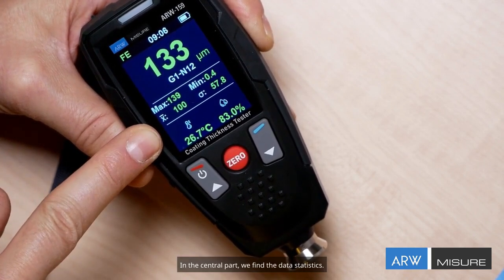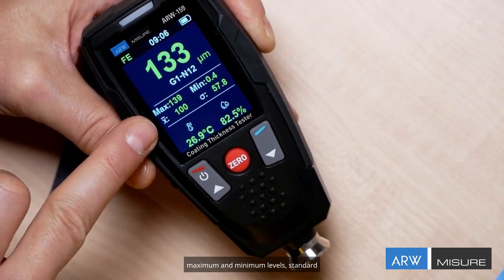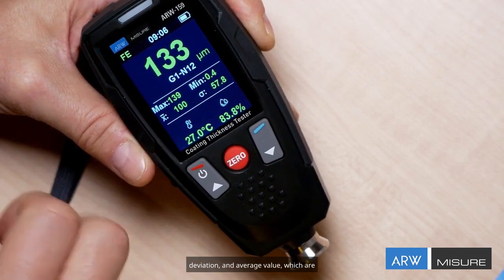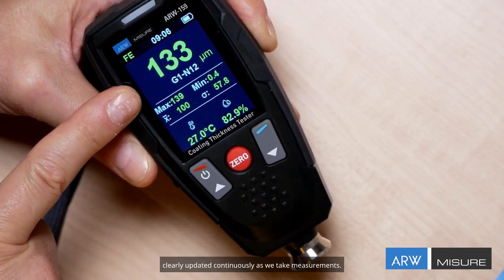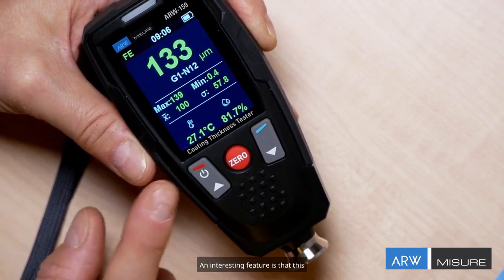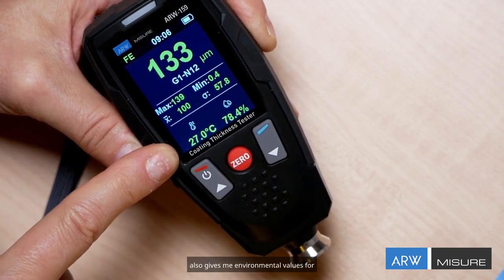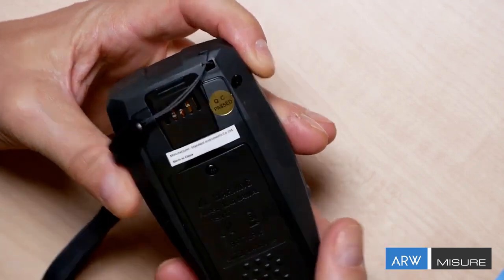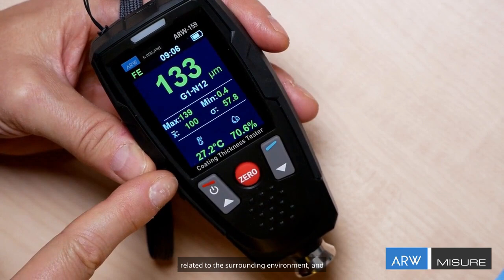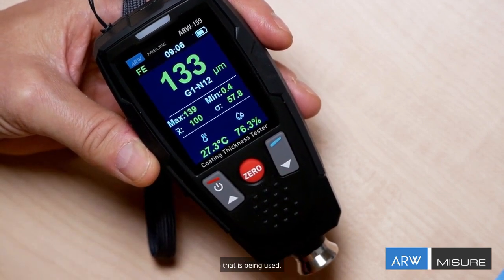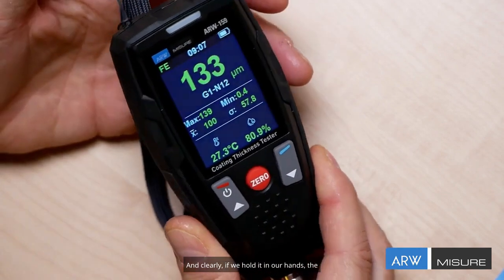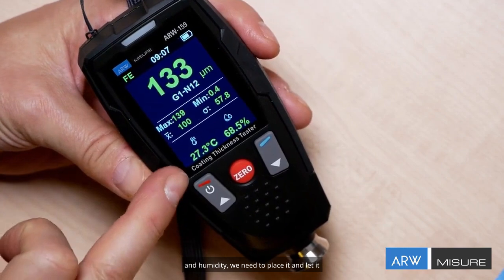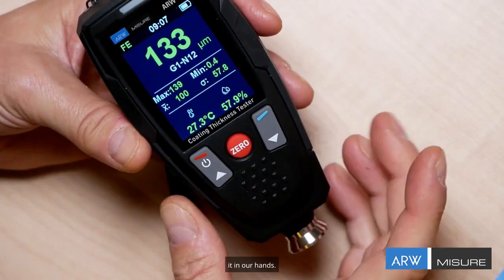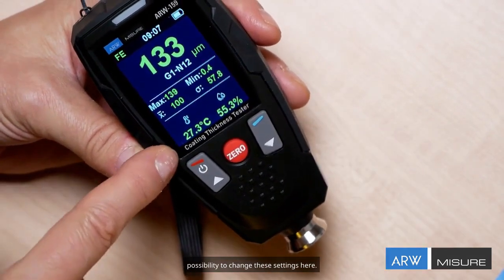In the central part, we find the data statistics. The data statistics allow us to see the maximum and minimum levels, standard deviation, and average value, which are clearly updated continuously as we take measurements. An interesting feature is that this instrument, as we can see in the lower part, also gives me environmental values for temperature and humidity. The sensor is located on the back. The data that we collect are specifically related to the surrounding environment and not to the material itself or to the probe that is being used. And clearly, if we hold it in our hands, the readings may be slightly affected by the temperature of our hands. Therefore, if we want to measure temperature and humidity, we need to place it and let it stabilize in the environment without holding it in our hands. Then we will see that we also have the possibility to change these settings here.